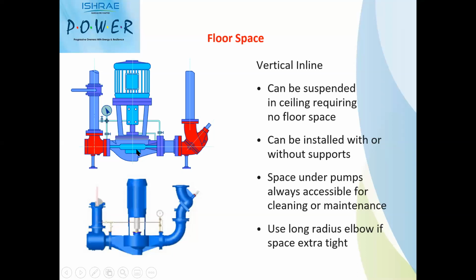When you are installing any vertical inline pump, it is a pipe mounted design. In most cases, bellows either are required or not required, depending on the manufacturer. Since the motor sits on top of the pump itself, this definitely consumes very little space compared to a base mounted pump. So it will definitely save you floor space when you install these pumps compared to end suction pumps.